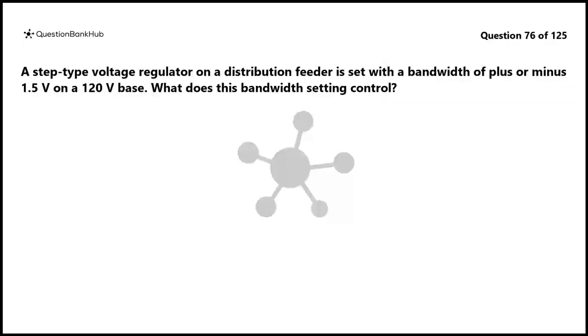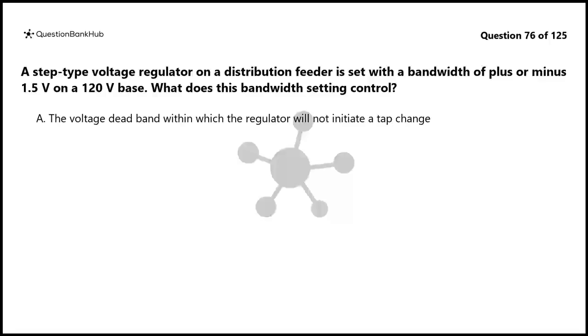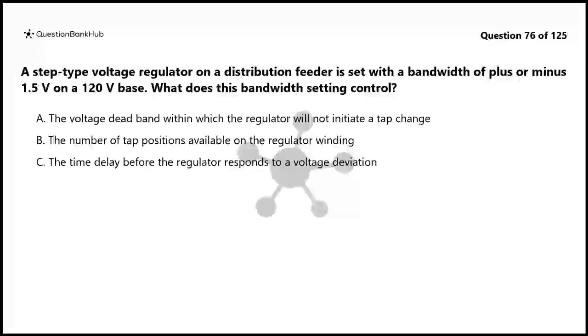Question 76. A step-type voltage regulator on a distribution feeder is set with a bandwidth of plus or minus 1.5 V on a 120 V base. What does this bandwidth setting control? A. The voltage dead band within which the regulator will not initiate a tap change. B. The number of tap positions available on the regulator winding. C. The time delay before the regulator responds to a voltage deviation. D. The maximum voltage the regulator can boost above nominal.